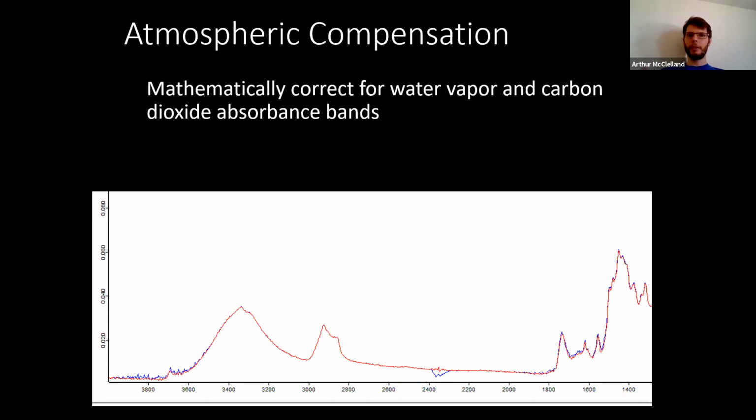One thing to be extra cautious of when you're doing FTIR is atmosphere. As I sit here and talk, I spew out water vapor, I spew out carbon dioxide. Carbon dioxide is the one that trips people up more than water vapor. Carbon dioxide is this set of peaks here. There are two really nice peaks right around 2350 wave numbers.